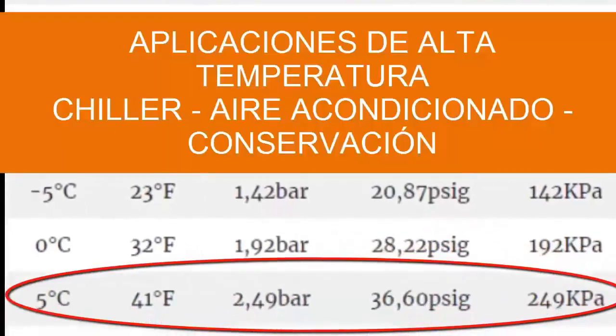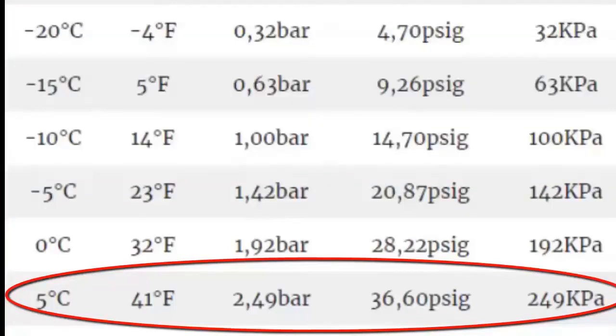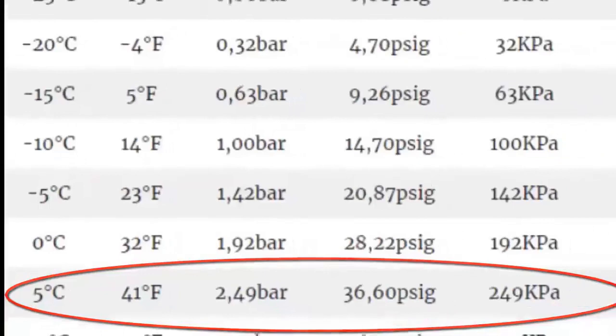5. To achieve a temperature of 5 degrees Celsius in the evaporator, equivalent to 41 degrees Fahrenheit, a low gauge pressure of 2.49 bars is needed, equivalent to 36.60 PSIG or 249 kilopascals.